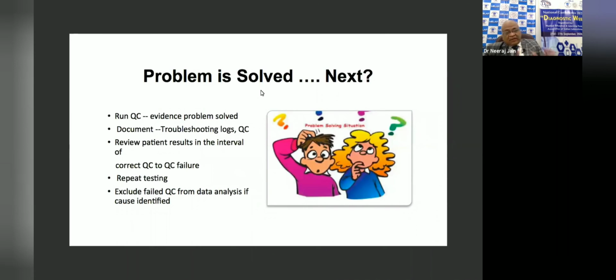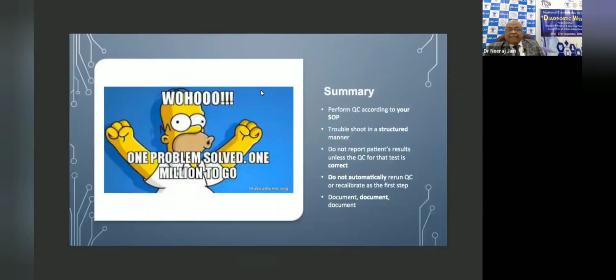So after solving the problem, you are running control again. But the important thing is, again I will emphasize, document, document, document. The important thing is you perform QC according to your SOP, troubleshoot in a structured manner. This we are talking about IQC. Do not report patient result unless you have corrected this QC failure, and do not recalibrate without any action.